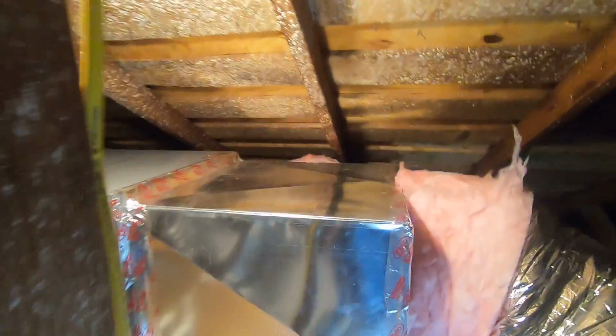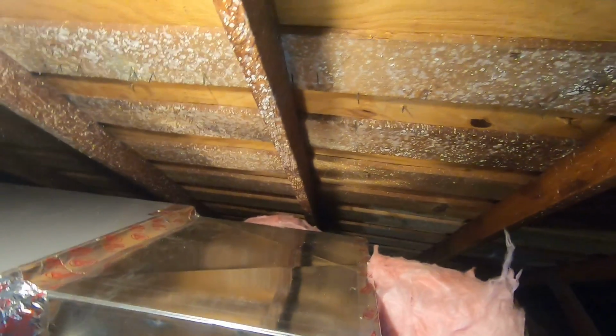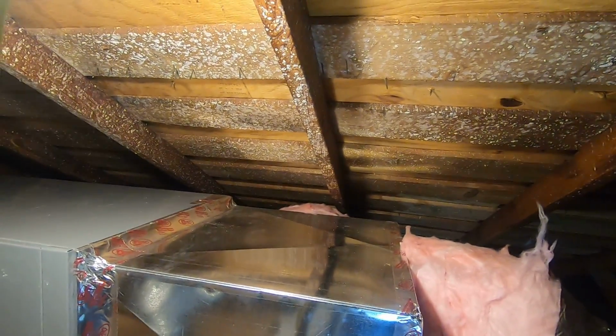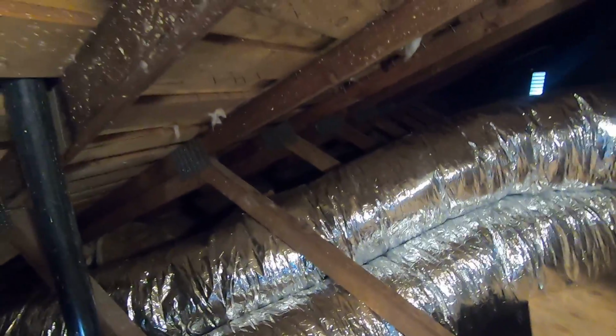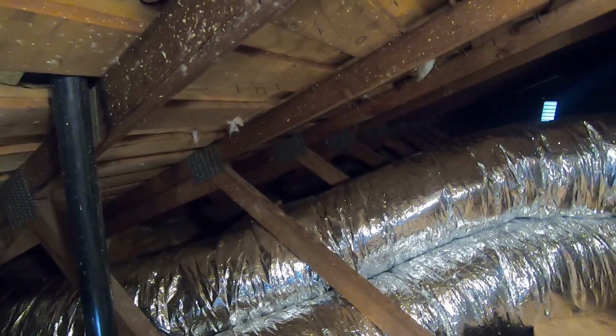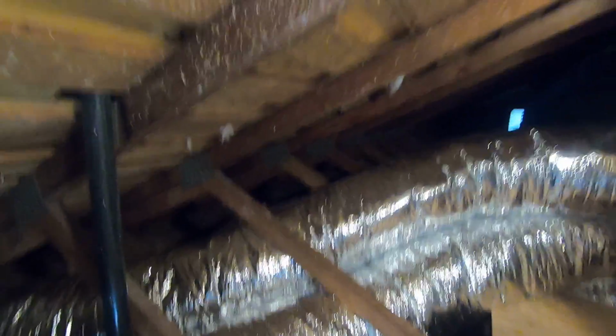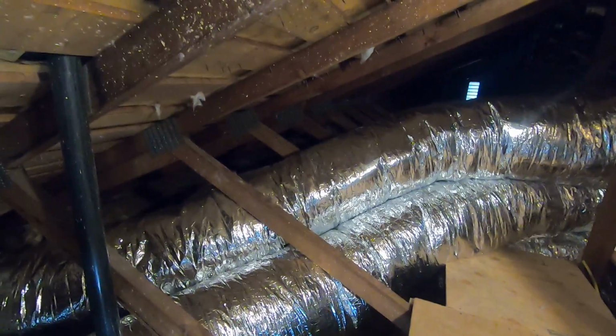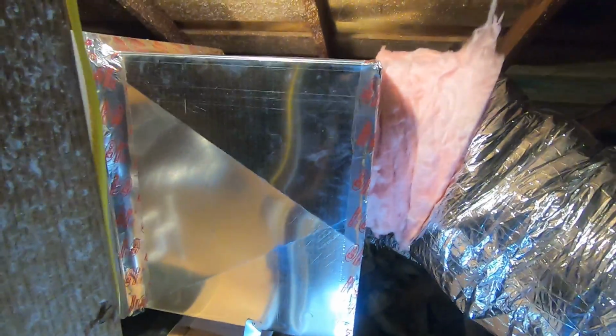And on the back side of this unit, it's very hard to see because it's a tighter attic on that side, but we cut another return off that side, and that goes over behind these ducts right here to a big return grill in the ceiling, and that's an 18-inch, so it's pulling 2,000 CFMs of air into the system. That's on the return side.